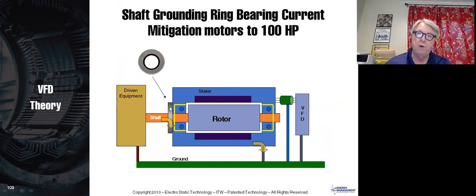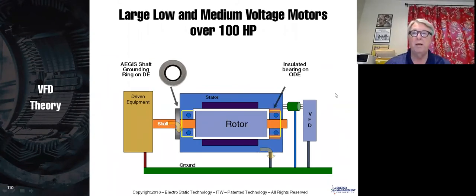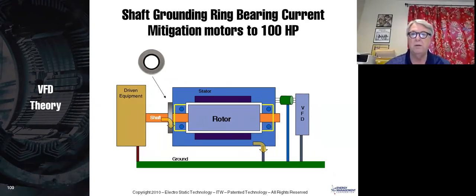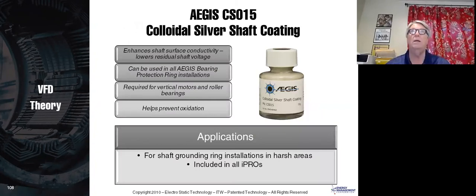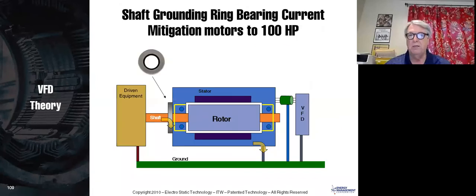Put one shaft grounding ring on the motor. Generally, the driven end is best up to motors 100 horsepower. If it's over 100 horsepower, we recommend an insulated bearing. I say we, that's Aegis. They're the only manufacturer of these shaft grounding rings, I mean. And then a shaft grounding ring on the other side. And in quite large motors, we're finding that we actually have to use 2 insulated bearings plus a shaft grounding ring. Now, let me mention, when you use that shaft grounding ring, we highly recommend that you make sure the shaft is smooth and you use a colloidal silver shaft coating where that brush touches it. And that gives it much better conductivity.